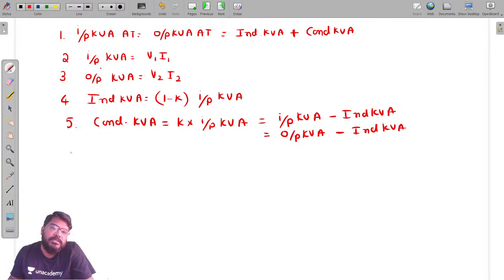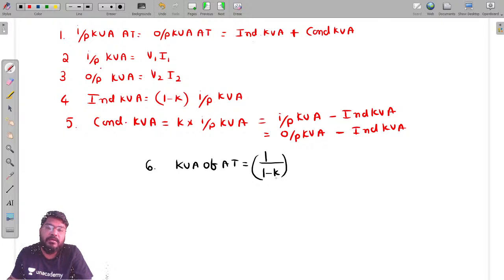From a comparison point of view, here's another formula for kVA rating in terms of the kVA rating of auto transformer. Suppose we know the two winding transformer's kVA rating and want to find the auto transformer's kVA rating, given the transformation ratio K, then kVA rating equals 1 over 1 minus K times of the kVA rating of a two winding transformer.